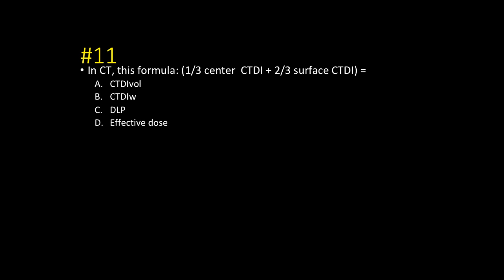Number eleven: in CT, the formula one-third the center CTDI plus two-thirds the surface CTDI gives you the weighted CTDI average. Most of the energy is deposited into the surface of the phantom or patient, so the surface component is more heavily weighted than the center.